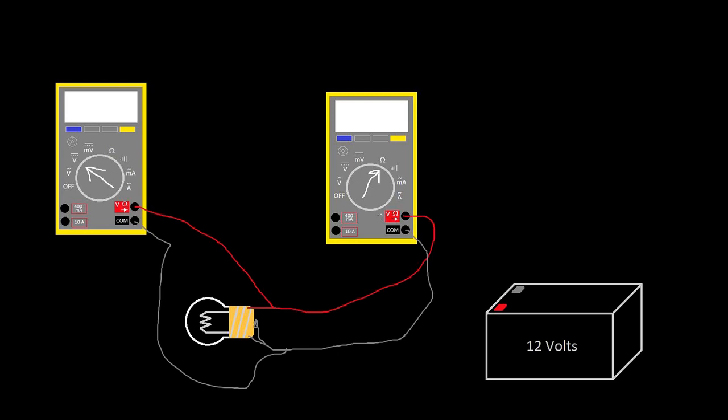So it's not much. Going off memory, it's about two volts or two and a half volts, three volts, something like that. But it's not a good idea to mix voltage sources. So before you start metering for resistance on a circuit, you're going to want to make sure there's no voltage on it. I'll usually set it to AC voltage, put my leads on the circuit. If I have nothing, set it to DC voltage, put the leads on there. If I have nothing, now I'm happy. I'll meter for resistance.